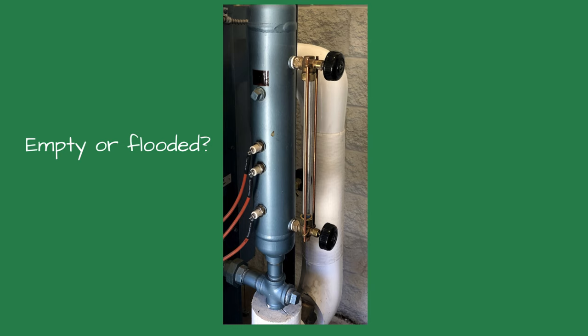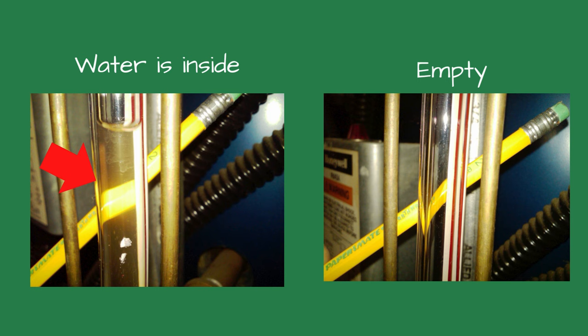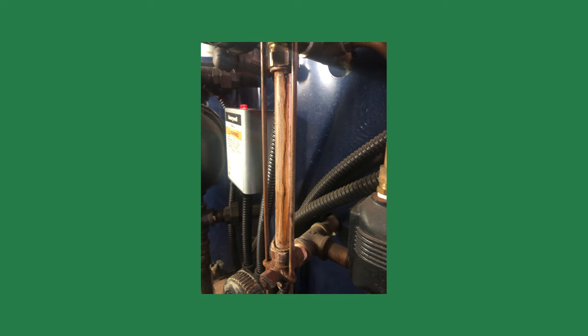Sometimes when looking at the gauge glass you can't see the water level — is the gauge glass empty or flooded? Remember, the gauge glass shows you the water level inside the boiler, and neither condition is good. Verify both valves are open. A trick I learned from Dan Holohan: hold a pencil behind the gauge glass. If the gauge glass is full, the pencil will appear broken at an angle. If it's empty, the pencil will look intact and straight.